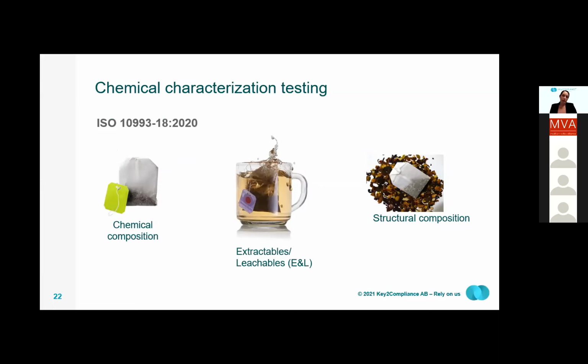So Part 18 of the ISO 10993 series describes different kinds of tests that you can do for the chemical characterization. So there are tests for looking at the chemical composition. That is what the material consists of and contains in total. What I think most people think of when you talk about chemical characterization testing are extractables and leachables testing. That is what may come out of the device, which I illustrate here with the tea bag. The distinction between extractables and leachables is that extractables are the substances that can come out of the device in a worst case or exaggerated laboratory situation, while leachables are the substances that will come out of your device during clinical use. There are also tests for looking at the structural composition of the device.